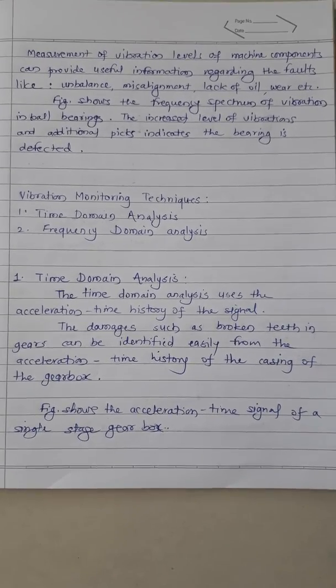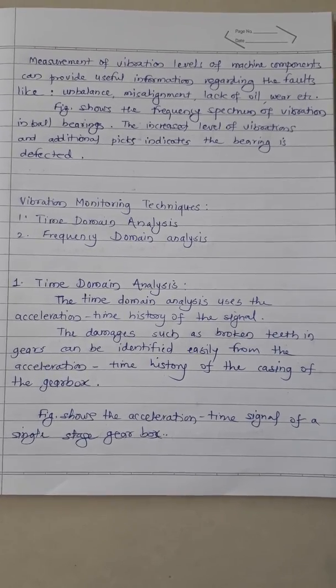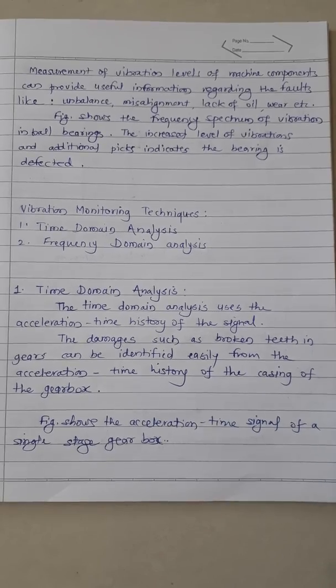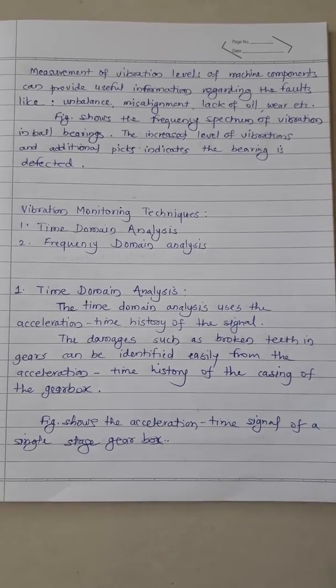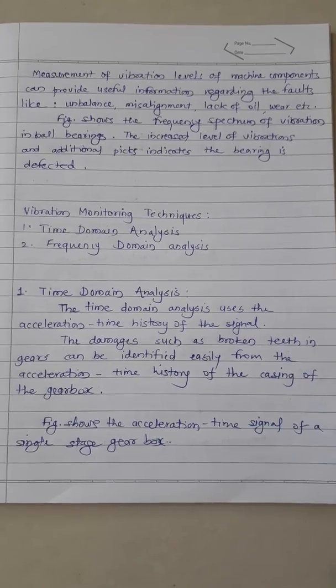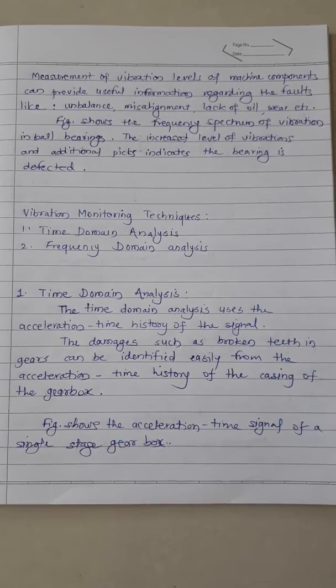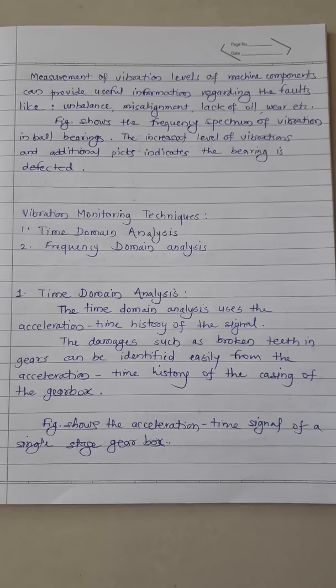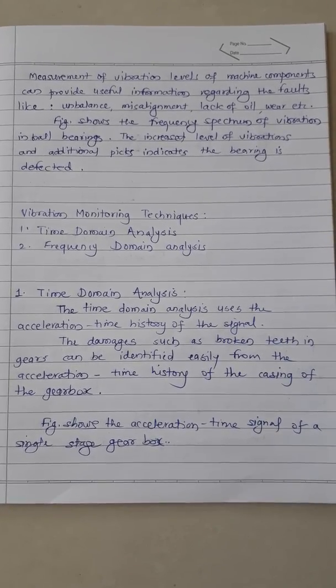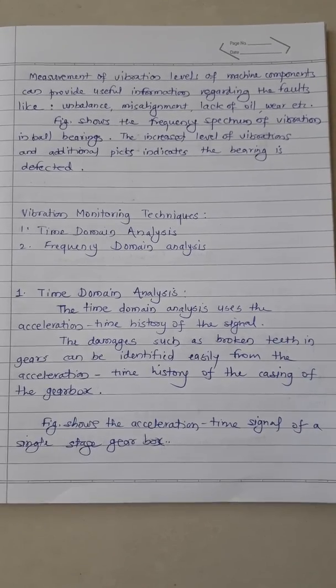Vibration monitoring techniques: 1. Time domain analysis. 2. Frequency domain analysis. Time domain analysis uses the acceleration time history of the signal. Damages such as broken teeth in gears can be identified easily from the acceleration time history of the casing of the gearbox. The figure shows the acceleration time signal of a single-stage gearbox.